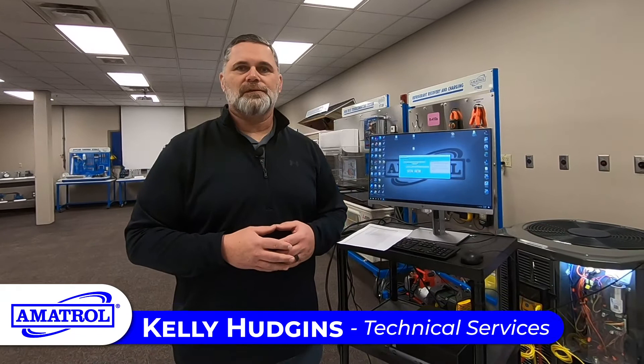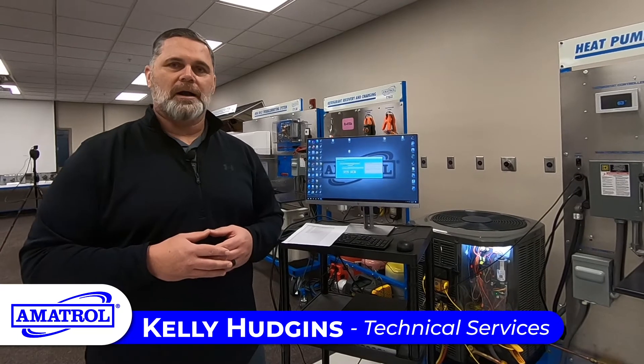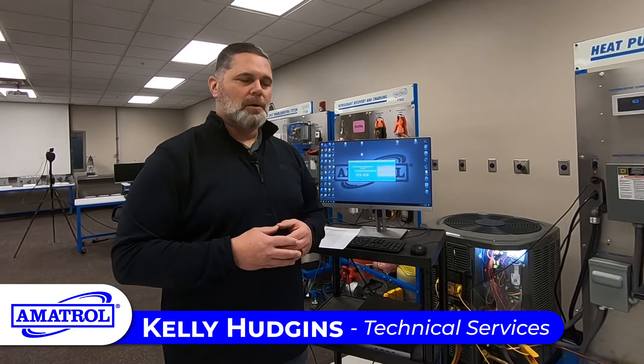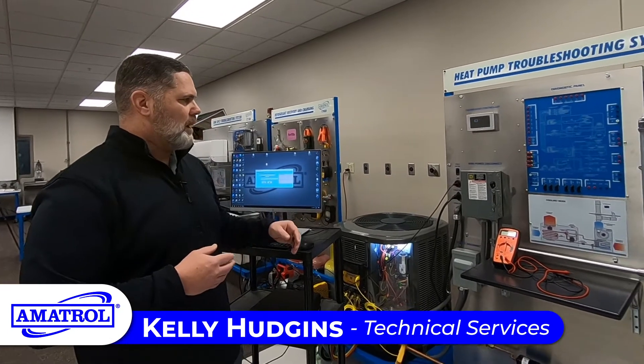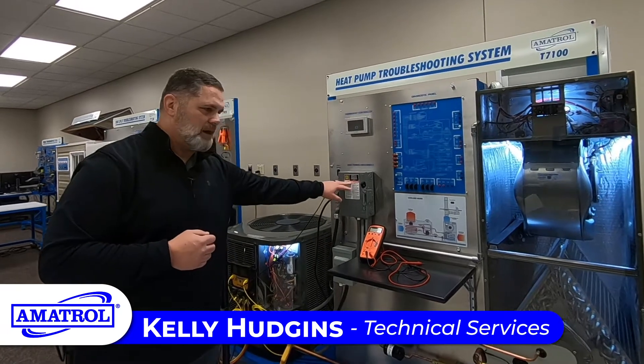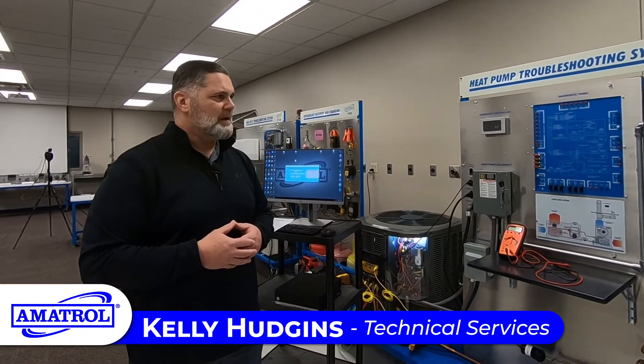The faults can range from a blockage of the system, or a simple thermostat issue, to a low voltage wire not connected properly. It can also diagnose a capacitor, fan blower, compressor, condenser fan, main power, and the disconnect box — the main power that you might find in the basement and the disconnect box that you would find outside next to the condenser.